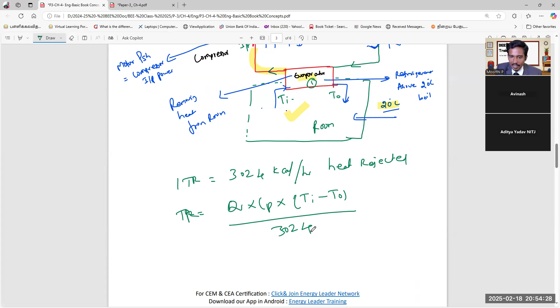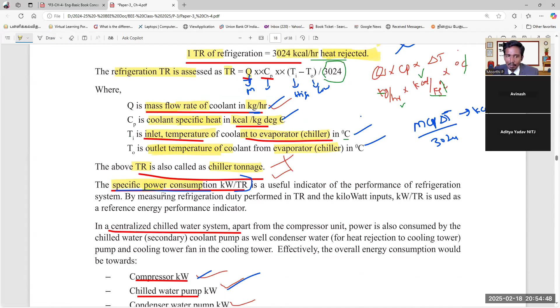Simple formula, always remember. Then specific power, very important: what is the compressor specific power consumption? Always remember, specific power consumption means power always comes first, kilowatt divided by CFM per compressor. Same concept, specific power consumption for the refrigerator system: kilowatt divided by TR. Understand? Yes, very important formula.